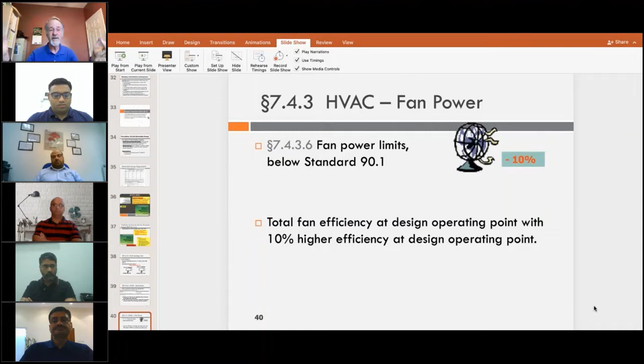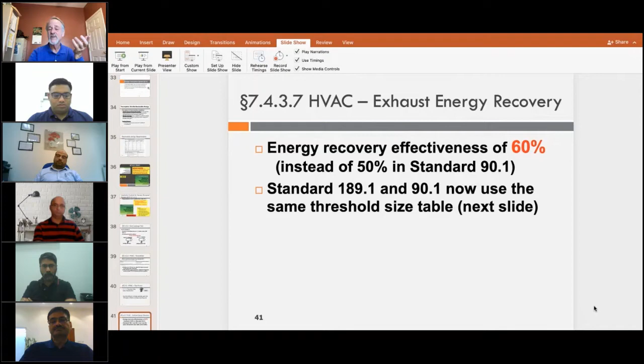Also, energy recovery, exhaust energy recovery. A minimum of 60% energy recovery effectiveness. That's a little bit higher than Standard 90.1. They still work on the same threshold tables. I don't want to spend a whole lot of time on this, and unfortunately, I don't have the SI version in terms of the flow rates. So basically, CFM divided by 2 gives liters per second, and there's a different criterion in terms of the climate zones, and that's how you look it up and work from there. So if your air handling unit, just one single air handling unit, is greater than this flow rate, you have to do energy recovery for that point.